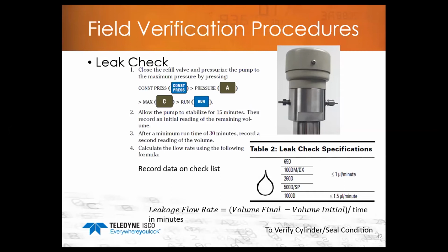We do have a seal bypass leakage specification on all of our pumps. So for the 260D, 500D, 100D, that leakage spec is less than 1 microliter per minute. Anything over that, we consider the pump not passing the leak specification. On the 1000D, we allow 1.5 microliter per minute bypass leakage. Anything above that, in our eyes, the pump would not pass the leak spec when you're running that leak test.